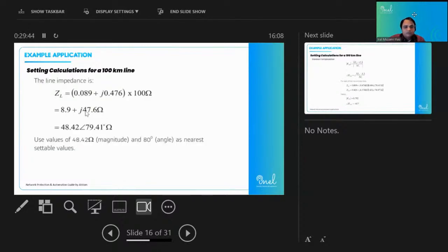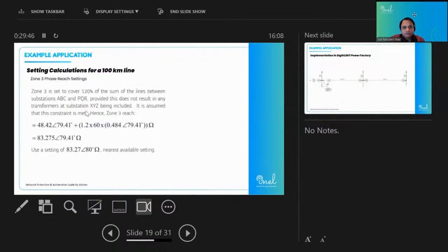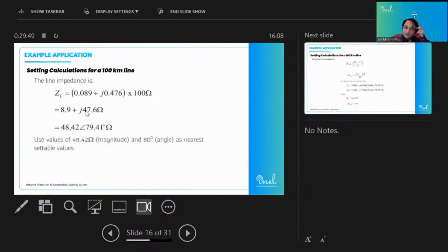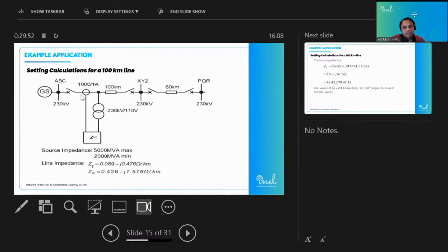So this is the basic principle for the calculation of the network settings. We will set 3 zones which will be forward looking zones. Zone 1 will be from point ABC to XYZ, but not exactly up to XYZ. It will be a maximum of 85% of ABC to XYZ. Like if this is 100 kilometers, then this Zone 1 reach will be a maximum of 85 kilometers. So from point ABC to 85 kilometers, this will be our Zone 1.